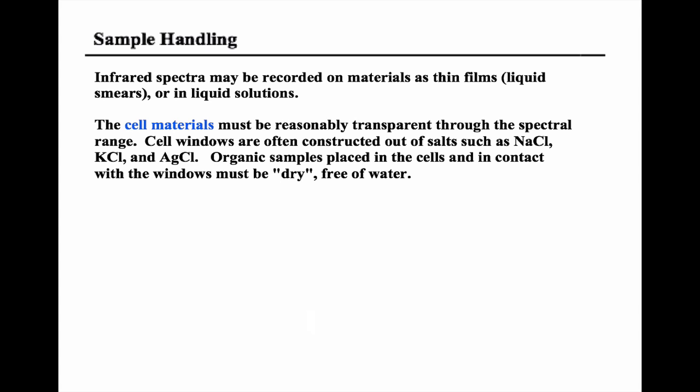Now, salt doesn't sound very expensive, right? But a single salt plate that we used to buy was $100. Okay? They are single crystals, huge single crystals of salt. They're about that big around. They're not like they just take salt and just pack it together, okay? What do you know about salt? What does it like to dissolve in? Water. What does the air have down here in the south? A lot of water, right? So you can't just leave these things out on the bench or they start to dissolve, okay? So there's $100 worth of salt getting ready to dissolve into 2 cents worth of salt, right? And so you have to store them in a desiccator that keeps the water away.